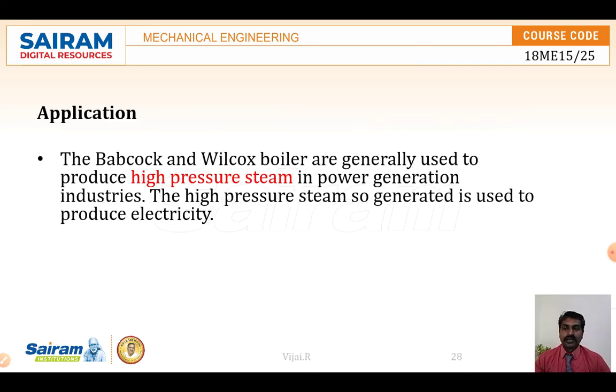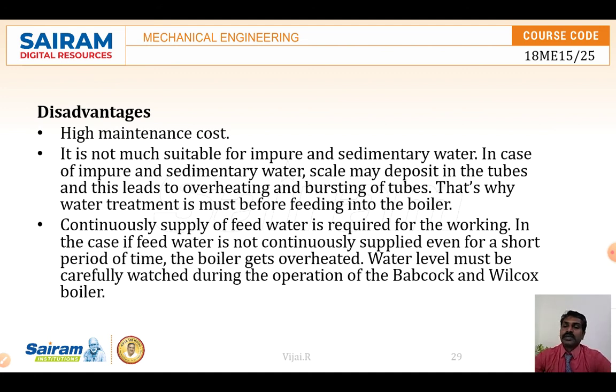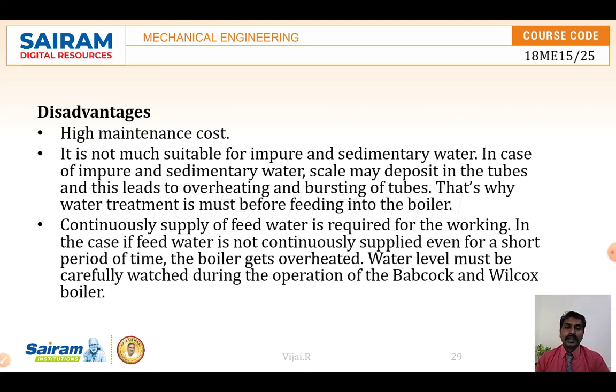The Babcock and Wilcox boiler is mainly used in industries requiring high pressure steam, particularly in power generation for producing electricity in thermal power stations. A disadvantage is that it is not suitable for impure or sedimentary water — water must be purified. Scale deposits can form inside the pipes, causing damage and restricting water flow. Therefore water treatment is important, and a continuous supply of feed water is required to prevent boiler damage.